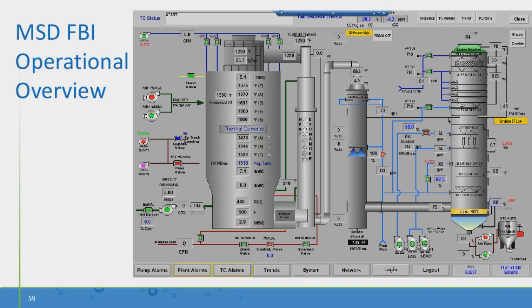So that air actually goes into the heat exchanger, where we have 2 functions simultaneously occurring: you heat up the ambient air, so to speak, and cool down the air that is leaving from the top of the incinerator and continuing to flow through the system. As you keep peering through the temperatures here, you can see the temperature continue to decrease as it rises up and out of the incinerator into the heat exchanger.